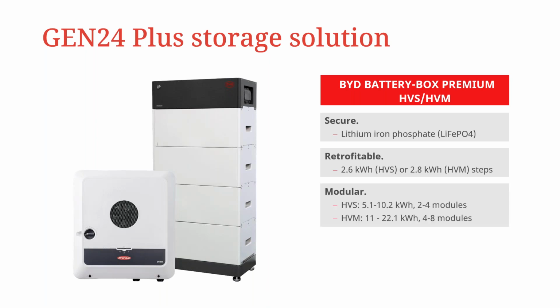They are modular. So the BMS is modular in a sense that you can do multiple power stacks. So you can have 5.1 all the way up to 10.2 kilowatt hours. So that's anything from 2 to 4 modules with one BMS. And then with the HVM, you can have 11 up to 22.1 kilowatt hours. So this is anything from 4 to 8 modules on one BMS. It's an easy installation, so it's a ground mount. So it's got a ground mount plate that the inverters and the batteries will sit on, apologies. And this also gives you easy commissioning with the Gen 24, as both are integrated to work.